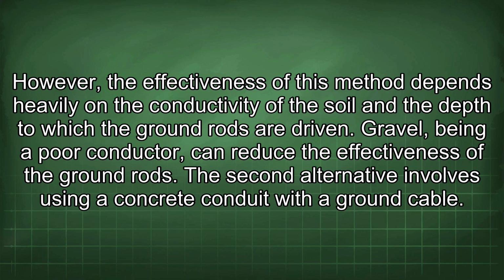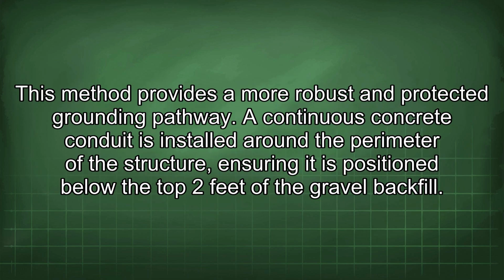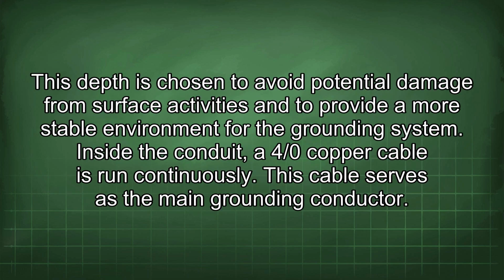The second alternative involves using a concrete conduit with a ground cable. This method provides a more robust and protected grounding pathway. A continuous concrete conduit is installed around the perimeter of the structure, ensuring it is positioned below the top 2 feet of the gravel backfill. This depth is chosen to avoid potential damage from surface activities and to provide a more stable environment for the grounding system. Inside the conduit, a 4/0 copper cable is run continuously.